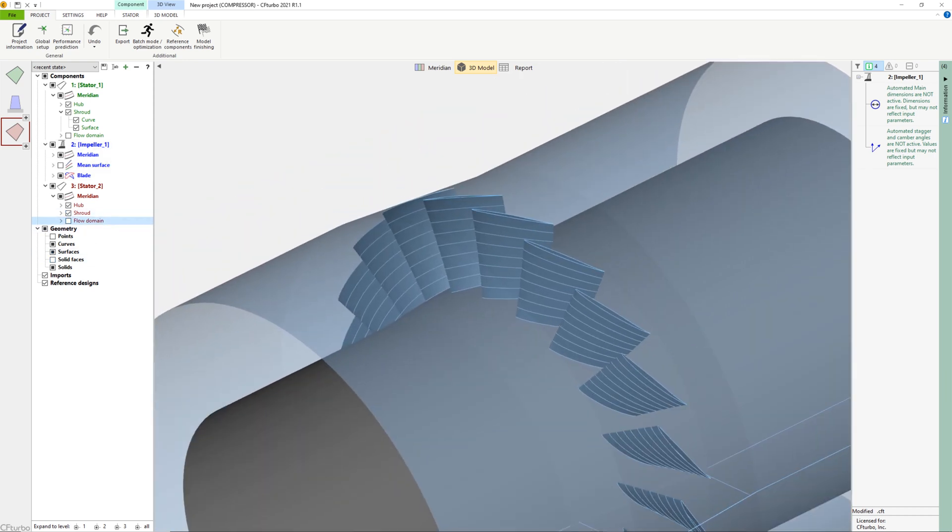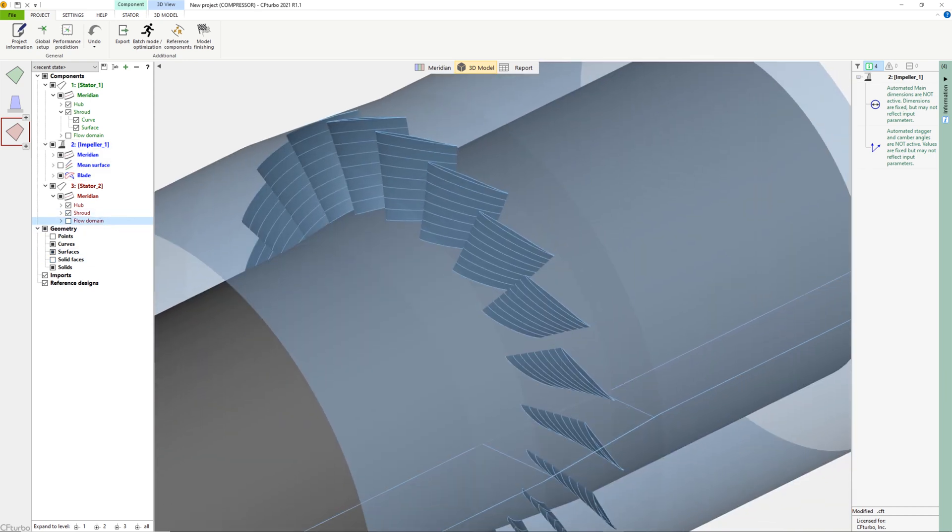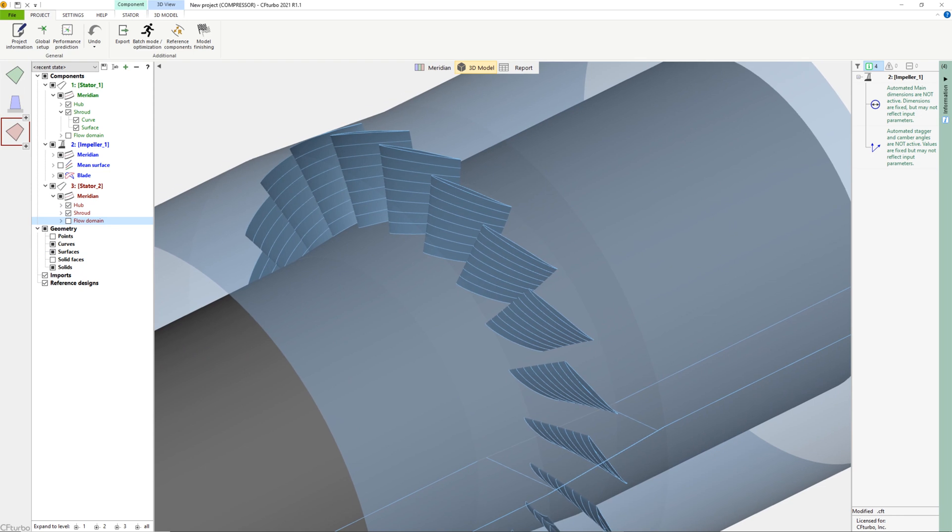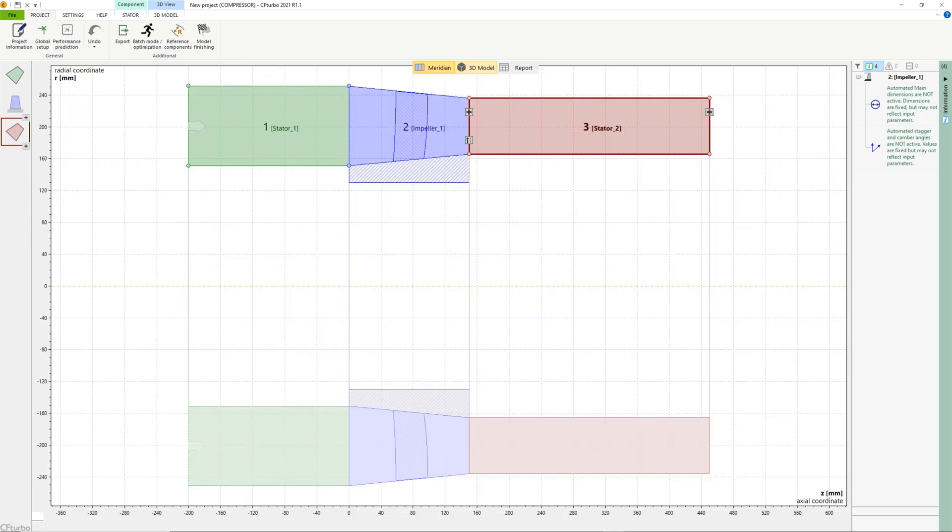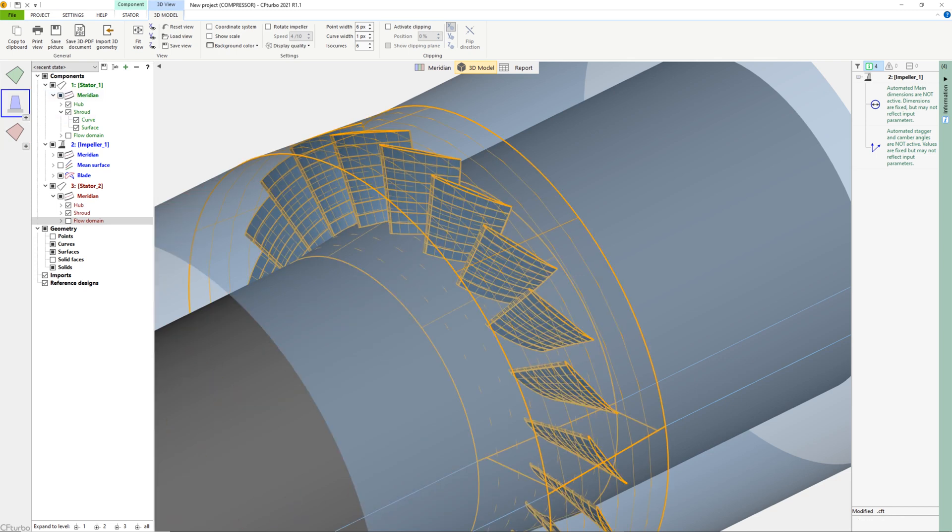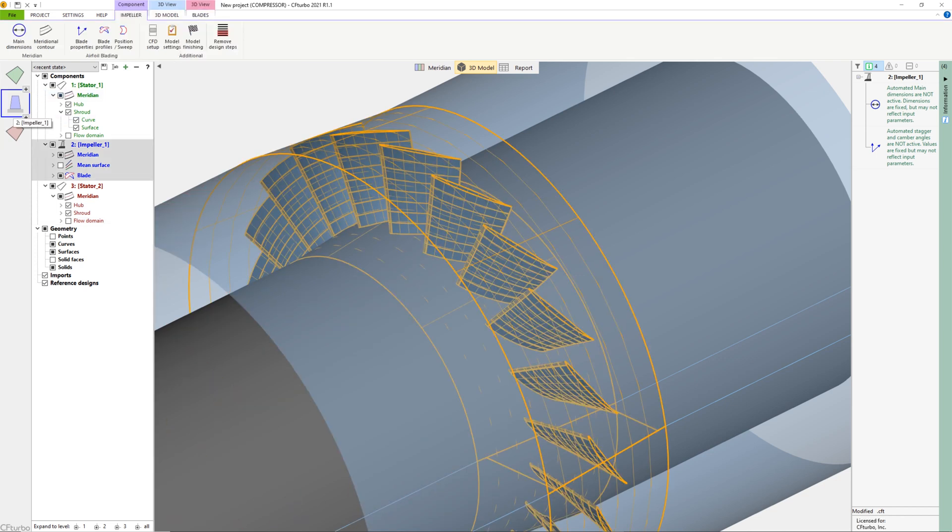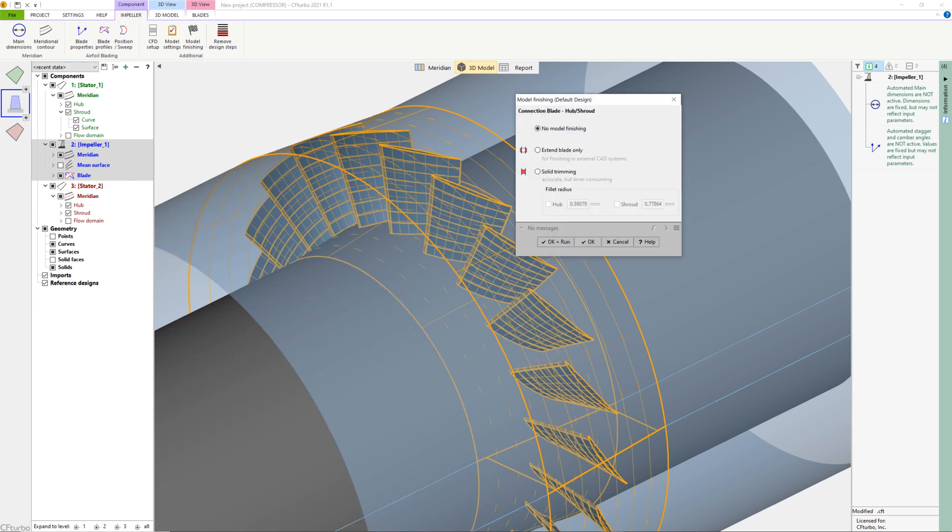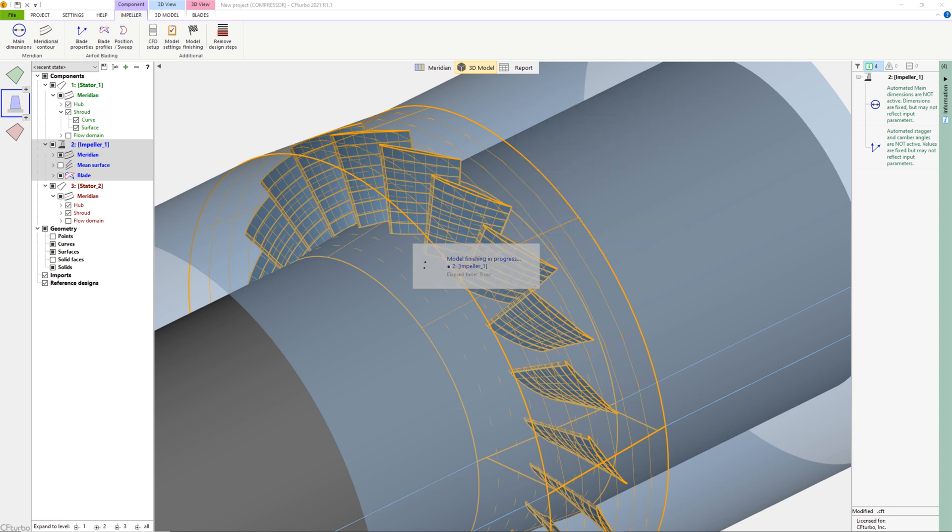The inlet pipe should have a certain length in order to prevent an impact from the boundary conditions to the fan stage itself when running a flow simulation. The outlet domain is recommended to be even longer due to the inherent swirl downstream of the rotor. Just like in the previous design steps, the model can be shown and updated in our 3D viewer.